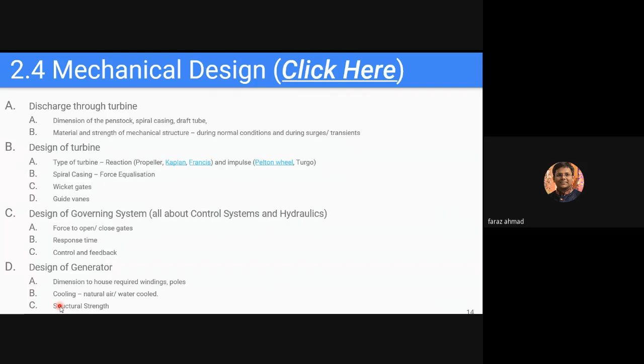The generator that we have installed has a diameter of nearly 10 meters. So just imagine a 30-foot long, 30-foot wide rotor just to house one 25 megawatt machine. Then when you have a rotor of that much width, you have to decide how many poles there should be, what the winding criteria should be, everything. Fine. Then cooling, natural air or water cooled, it is up to you. Structural strength: you cannot just make a 500 megawatt machine with a design that is bearable for 100 megawatt.